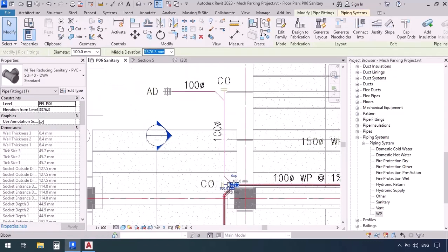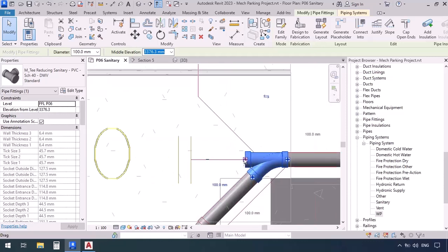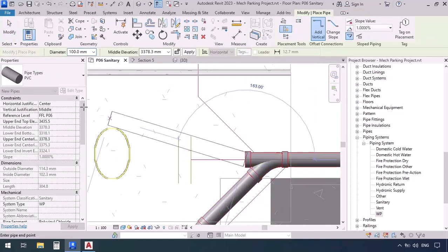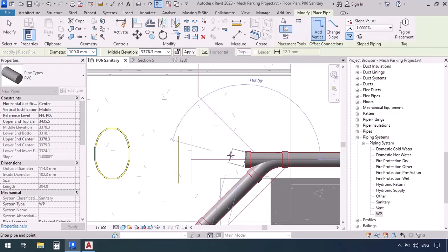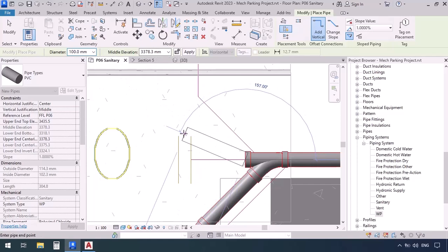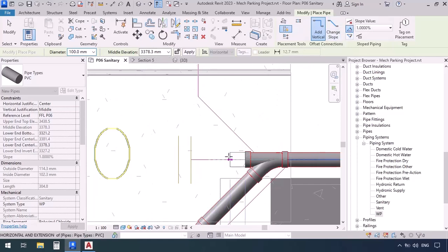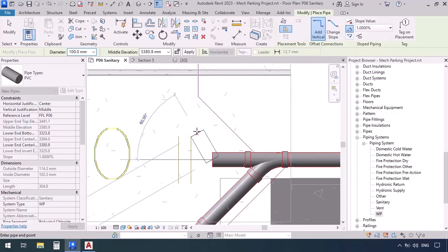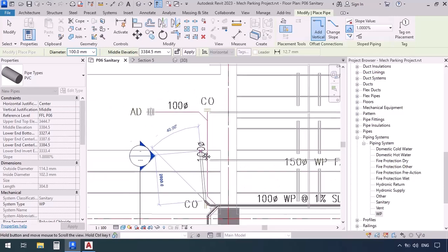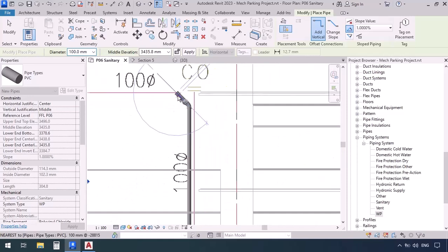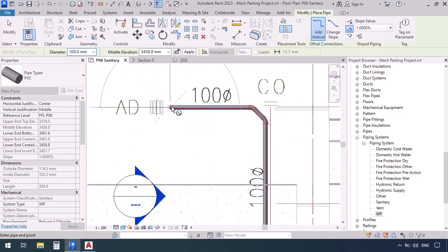Now to continue, we're going to calculate a little. We want to draw from here and go up to get close to the area drain. Getting close has a positive meaning, so our slope needs to be up. We're going to go to our starting point, right-click and click on Draw Pipe. We've already checked the fitting type, system type, and size. This time we don't need to enter an elevation — once we click Draw Pipe it gets the elevation of its starting point. Slope is up and we've checked all five items. We'll click straight ahead, give it an angle, go up, click, then at a 45-degree angle click, and then near the area drain click and press escape.